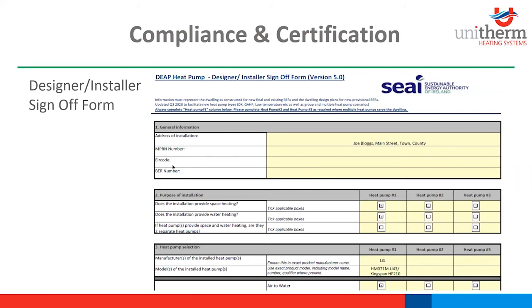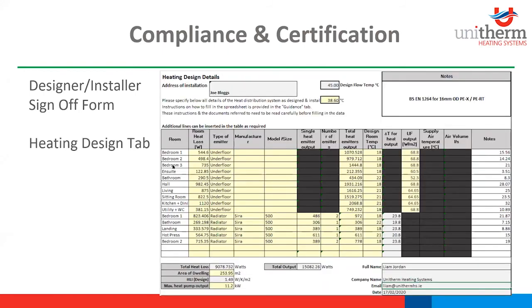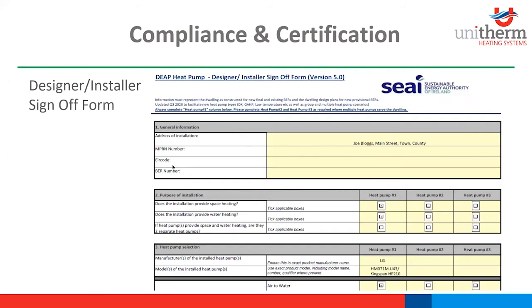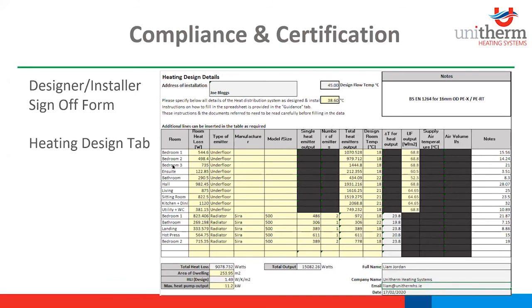Designer installer sign-off form. So basically just signing off each project. So it states the type of heat pump installed and the project, and verifies running parameters. The designer installer sign-off is needed by the BER assessors, as these parameters are entered into DEAP 4.2 to quantify the heating and hot water performance. So this is just a basic example of it there for your LG Therma V 7 kilowatt.